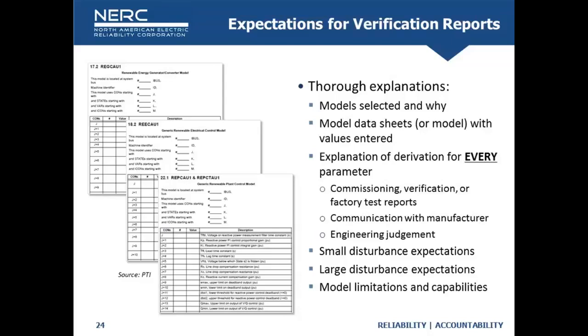So you have small disturbance expectations, and you need to understand the model limitations and the capabilities of the models. There are things that are not modeled, and we know that, and that should also be described. And maybe that's coming from the equipment manufacturer saying, well, I give you a model, here's what it is intended to be used for, here's the extent to which you can use that model in simulation, and here are things that you can't typically represent. Some of the drivetrain dynamics, for example, on a wind machine may not be accurately represented in the generic models. They may be, they may not be, and we need to understand that.